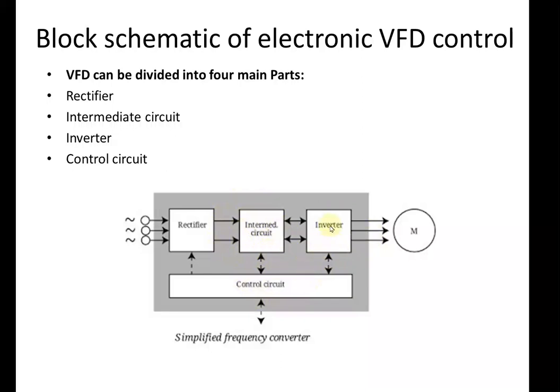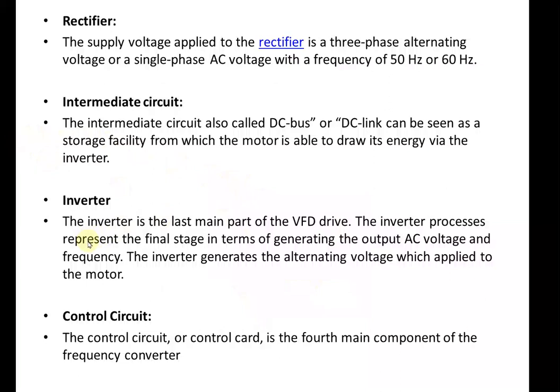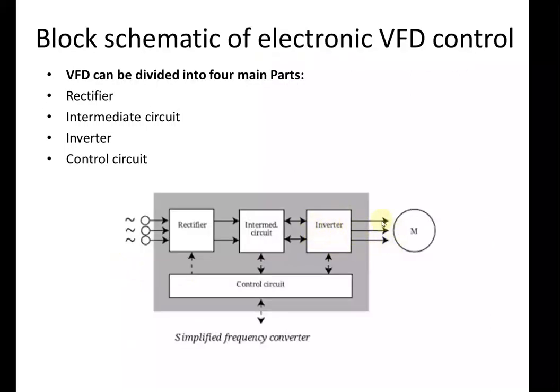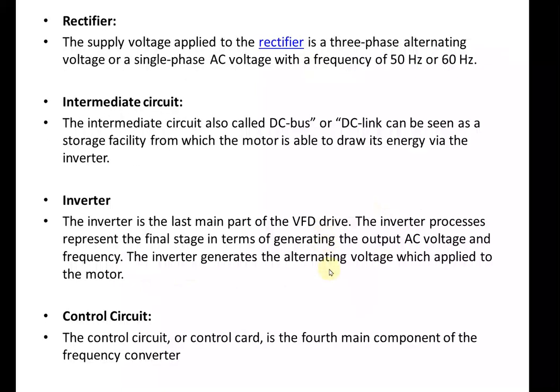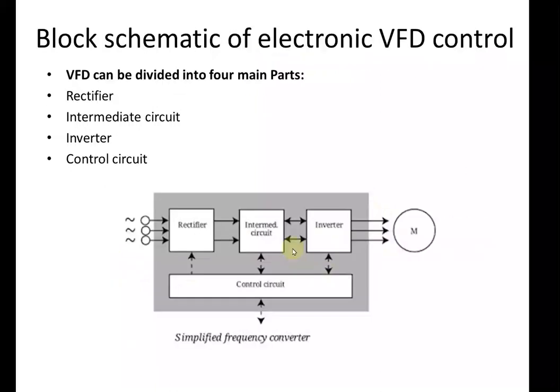The third part is the inverter — the main part of the variable frequency drive. We require the input voltage to the motor to be alternating, so this is the main stage. The inverter represents the final stage in generating the output AC voltage and frequency. It takes the input from the intermediate circuit — which is pulsating or pure DC voltage — and gives alternating voltage to the motor, because the motor requires AC voltage at its input.